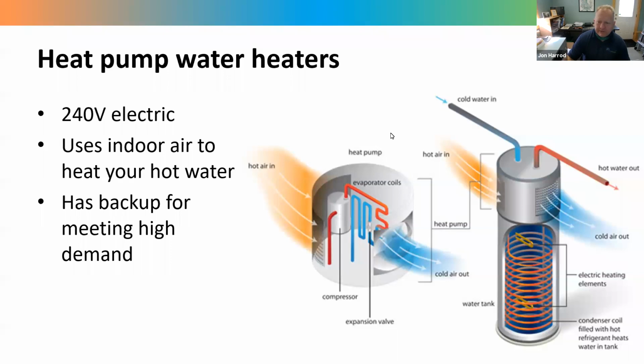So what these do is they pull in air from the surrounding space, they pass it over a coil that absorbs heat. Inside this is essentially a complete heat pump, including a compressor, evaporator, and the condensing coils that release the heat are down in the tank itself. These also have backup heating elements so that in times of high demand, they can fall back on conventional electric resistance. But when they're operating in heat pump mode, they are oftentimes 3 or more times more efficient than electric resistance. And so can cut the portion of people's bill that's for electric hot water significantly. They also represent a highly cost-effective replacement for people that are using propane or those rare cases that are using fuel oil to heat their hot water.